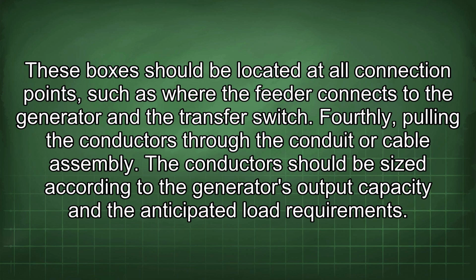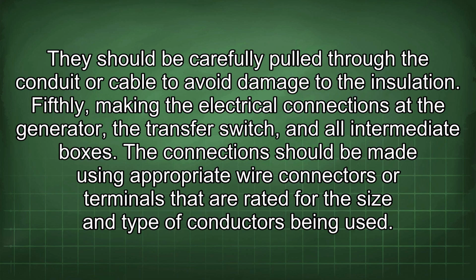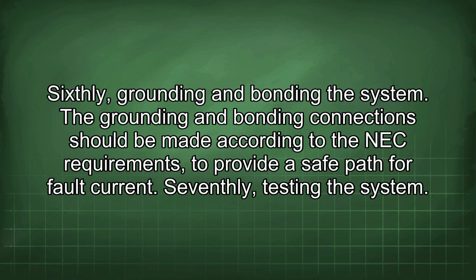The conductors should be sized according to the generator's output capacity and the anticipated load requirements. They should be carefully pulled through the conduit or cable to avoid damage to the insulation. Fifthly, making the electrical connections at the generator, the transfer switch, and all intermediate boxes. The connections should be made using appropriate wire connectors or terminals that are rated for the size and type of conductors being used. Sixthly, grounding and bonding the system. The grounding and bonding connections should be made according to the NEC requirements to provide a safe path for fault current. Seventhly, testing the system.